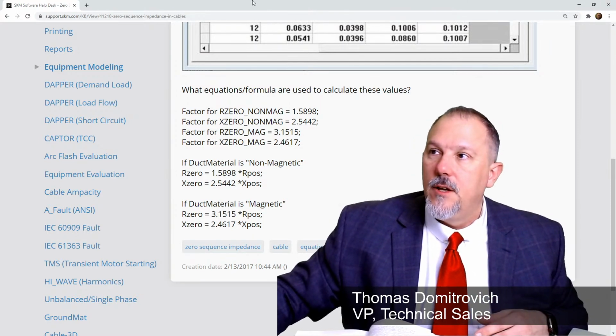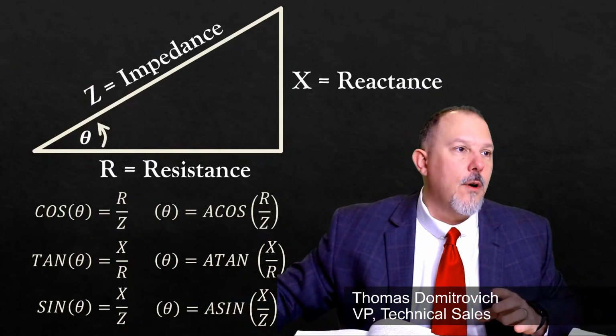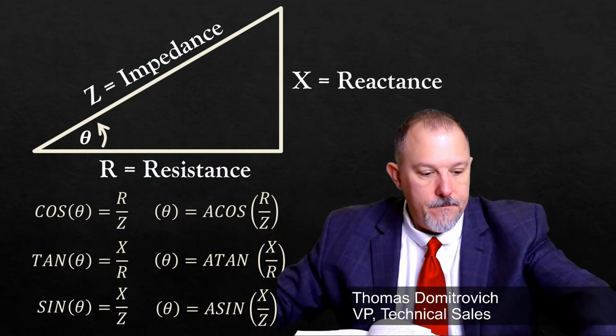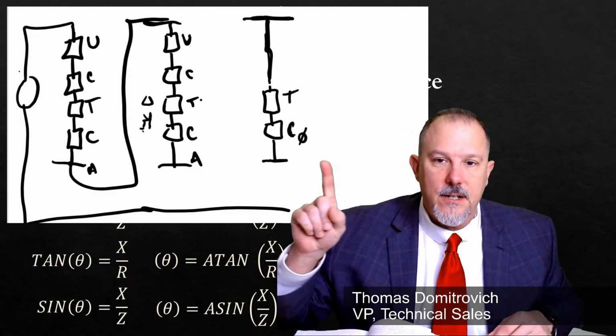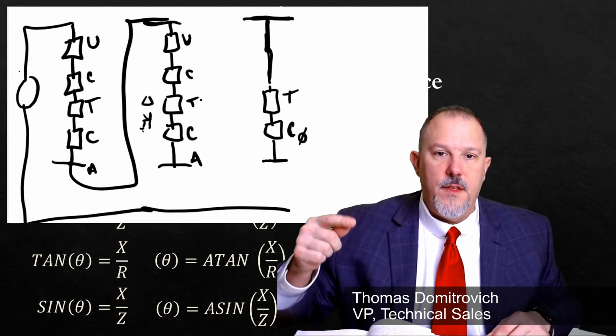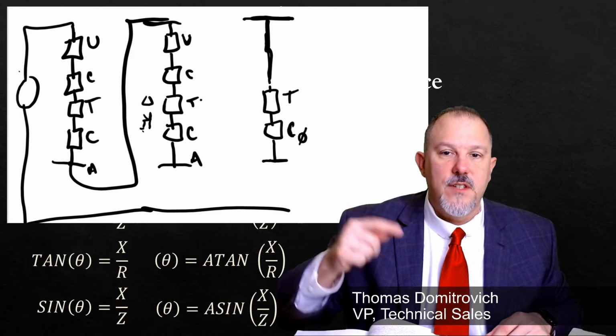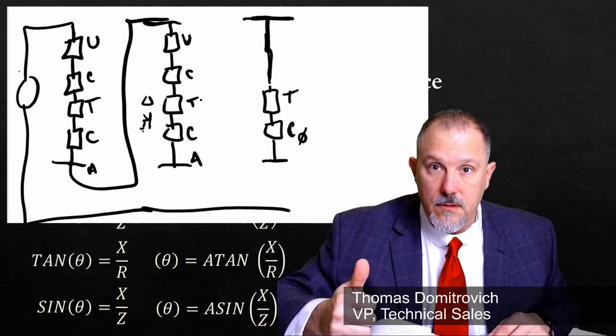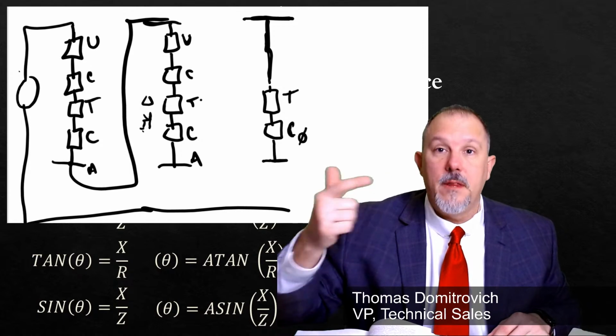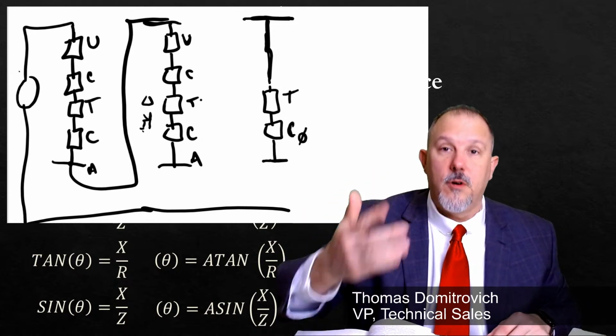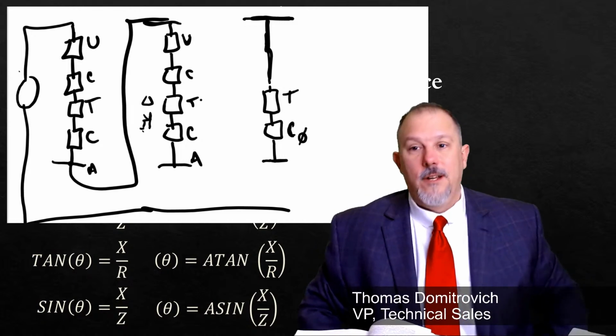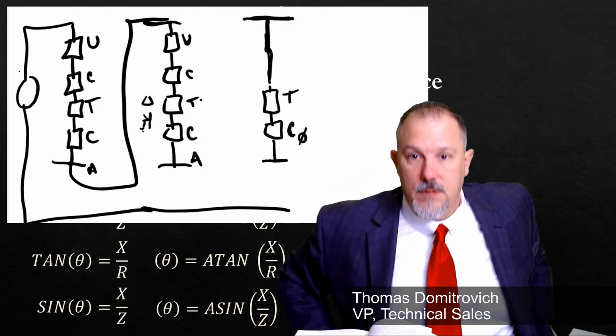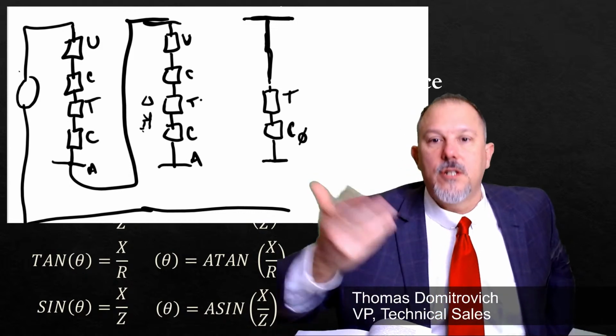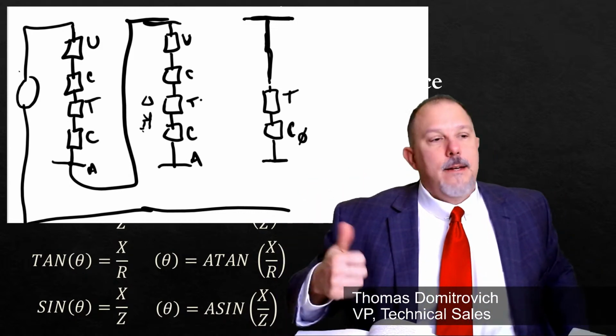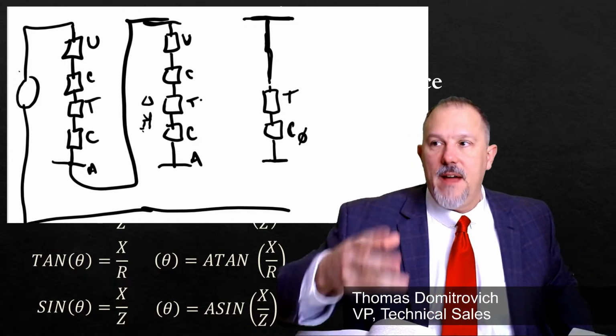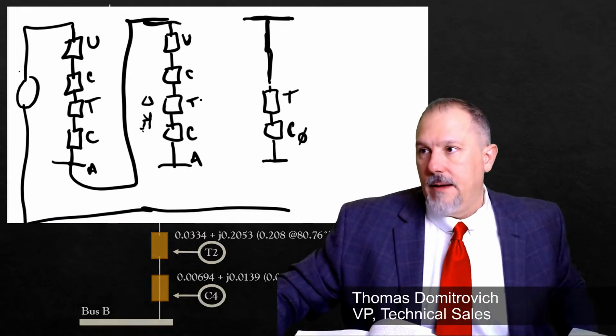But in any case, the reactance value for our impedance diagram for that conductor is going to be different than the reactances for the positive and negative sequence conductors, based upon the magnetic raceway and the multiplying factors. Again, what I used to do to get me in the ballpark, I would do 3 times. But now I'm going to start using the multipliers that they use. Those guys are pretty smart, and they probably have the math and their reasoning behind that.